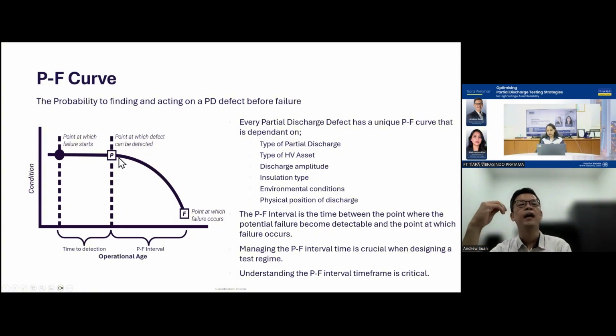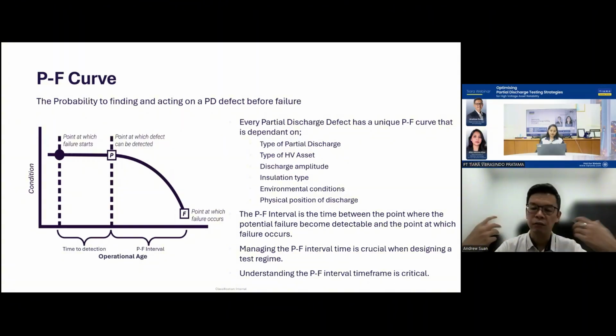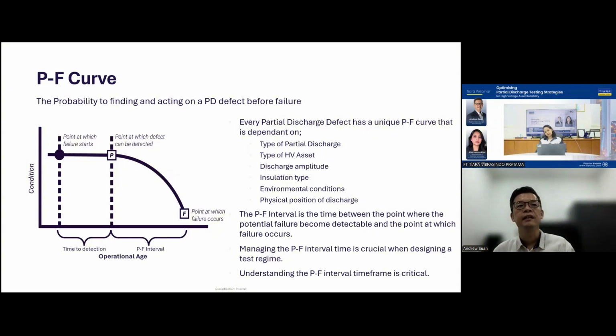The point where you're able to pick it up, we say this is the point where I can detect the PD already. Then I ask myself, from this point of detection to the point of failure, how long do I have? Do I have enough time to wait for the next shutdown, or do I need to quickly de-energize the machine and open it up to see what the problem is? If I don't do it now, maybe tomorrow it will flash over - is it that serious? We don't know. Every time in this kind of situation, we're all guessing and not sure.